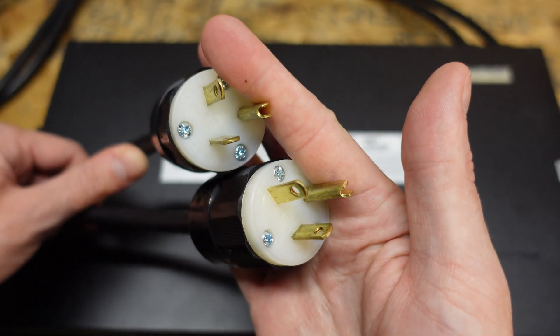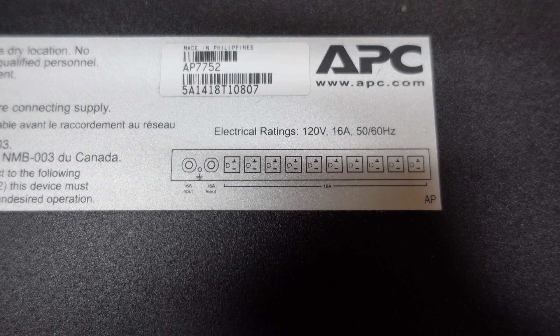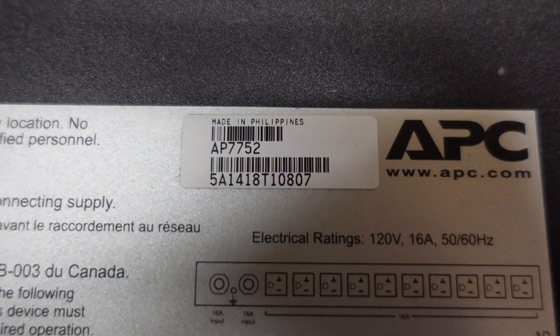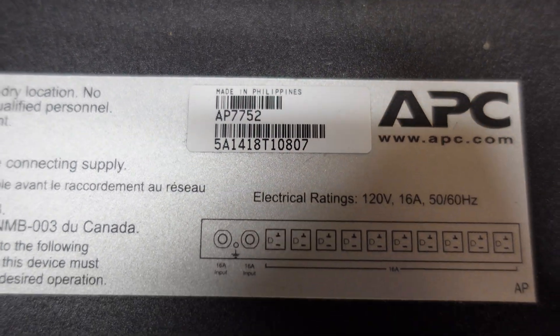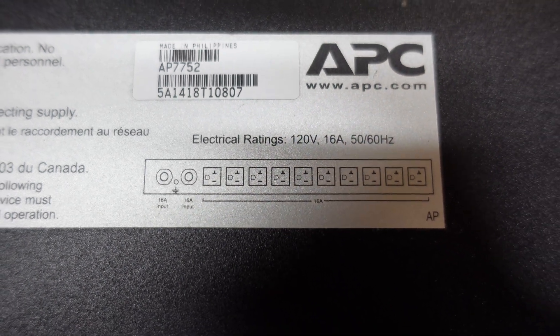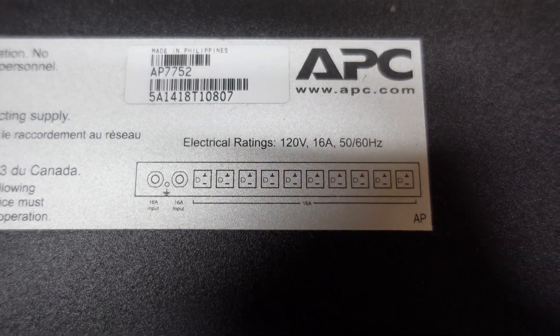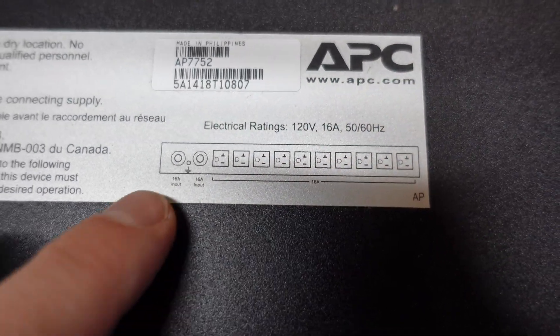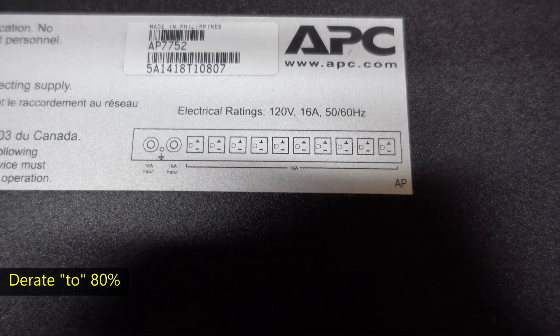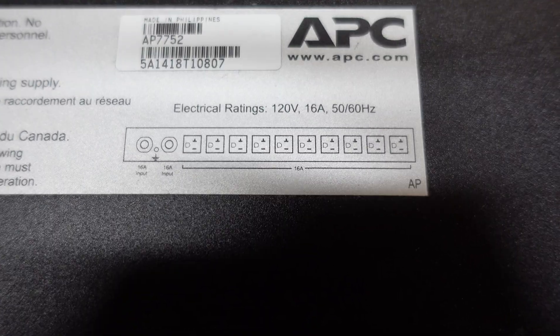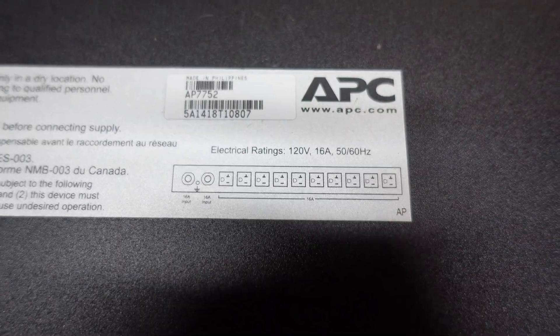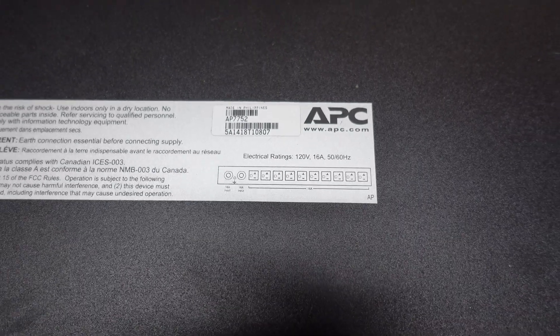This is a 20 amp receptacle, a 5-20. So taking a look at the top of the unit here, again, this is model number AP7752, 120 volt, 16 amp. It is a 20 amp transfer switch, but because we derate continuous loads by 80%, that gives us 16 amps. That derating is standard on any wiring circuit pretty much.